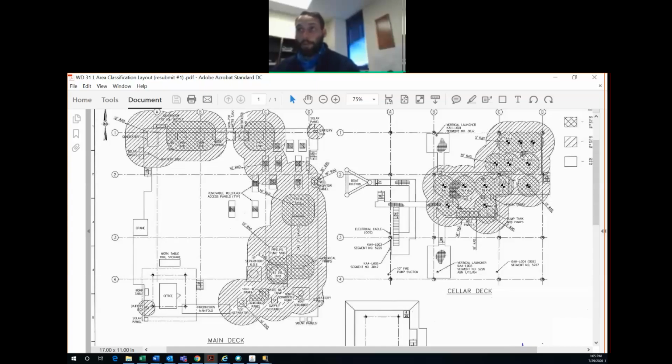That is going over a certain piece of equipment. So you'll notice that above the atmospheric chemical tanks, these probably chemical tanks containing a class 1 liquid, and that means that the liquid is flammable under 100 degrees F. And so you can see that there's a vent above these tanks that creates a class 1 div 1 area.